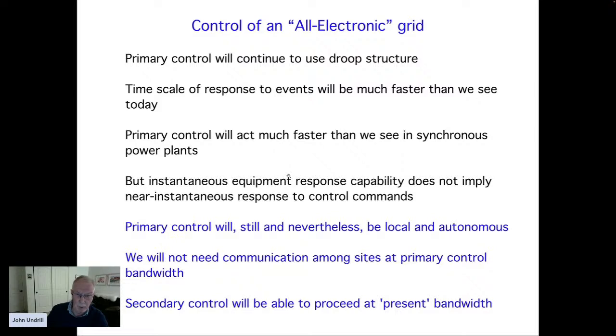We were sampling the signals that we needed to measure at a rate of 60 times per second. We were perfectly okay with respect to Shannon's theorem and sampling theory, but the 100 milliseconds of transport delay, that is latency, that we were getting between the signals being sent and signals being received was enough to destabilize a controller that we had on one of our engines and generate an unstable oscillation. And so I'm very, very much concerned that we can get the control of this system without depending on broadband with low latency communication. We want the control systems in these widely spread places, 1,000 miles apart, to be able to act autonomously and act correctly when they act autonomously.